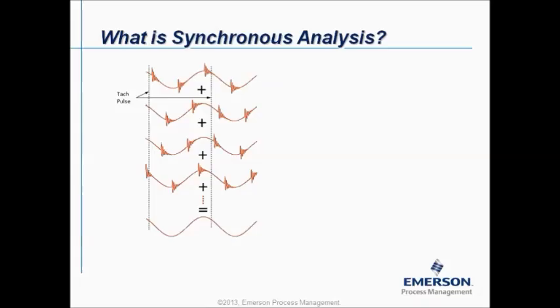Normally when vibration data is measured, a process called average is executed. During data collection a vibration channel is coming in, a period in the time domain is collected called a snapshot and based on this snapshot normally a spectrum is calculated. This process is repeated several times and then all the spectra are averaged and the final spectrum will be stored. And it will be an average spectrum.